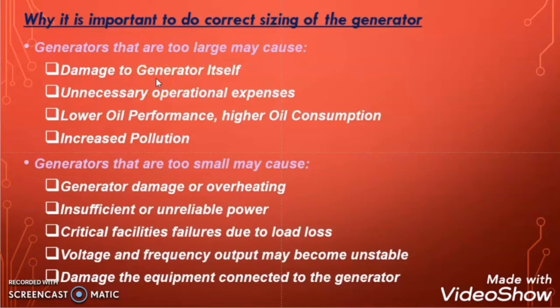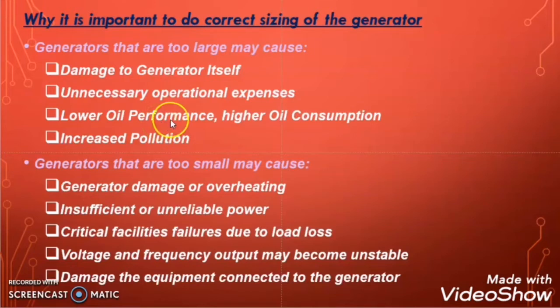Why? Because when the genset is under-loaded, it has to work harder to reach its operating temperature for better fuel combustion. As a result, the generator will be under huge stress. Even though the generator tries to achieve the operating temperature, due to under-loading it will not meet it. When the generator does not meet its operating temperature, fuel combustion will be partial, and due to this partial combustion the unburned fuel creates a thick syrup-like substance that slowly blocks the piston ring and finally damages the genset.